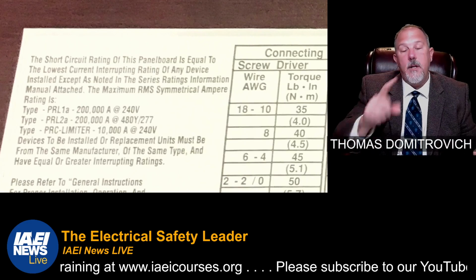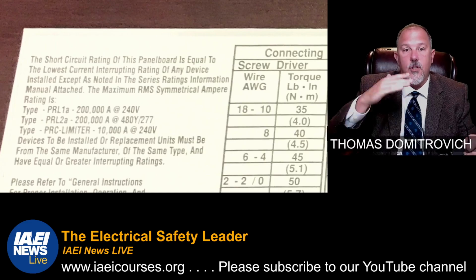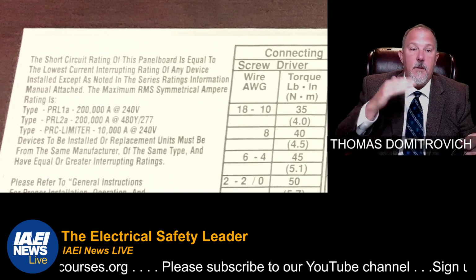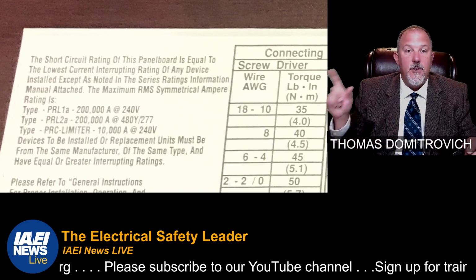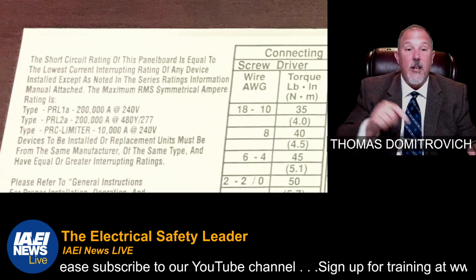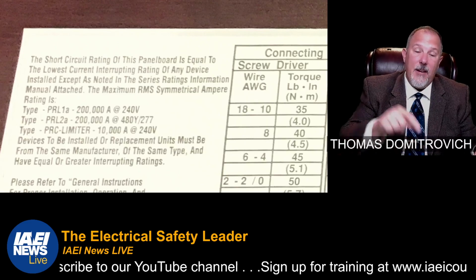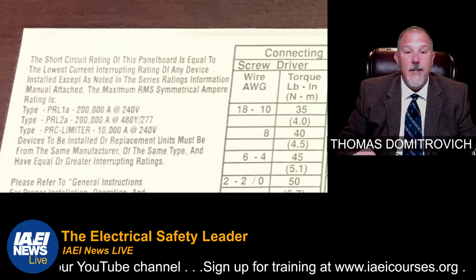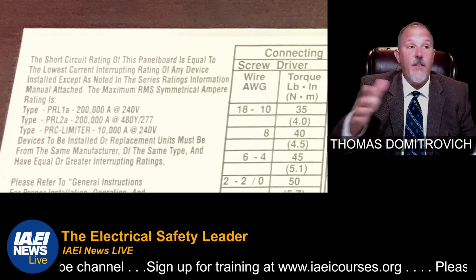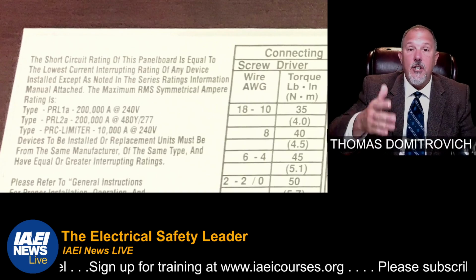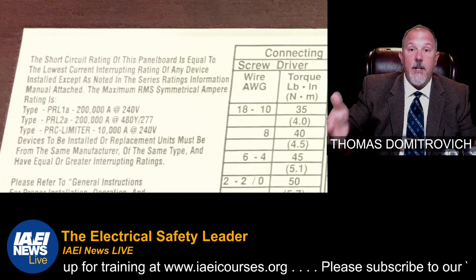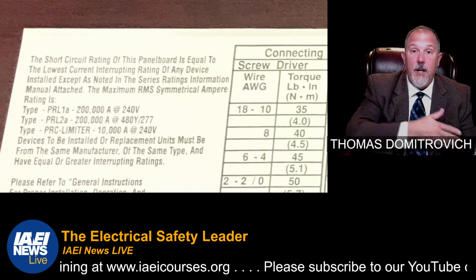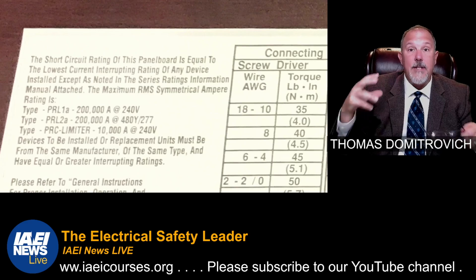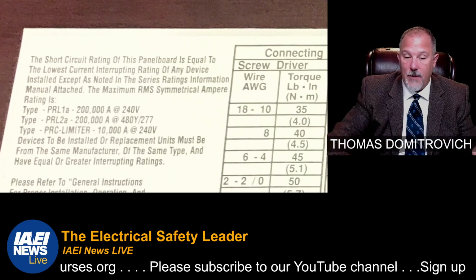And the moment you put it in that panel board, you've lowered the short circuit current rating of the panel board, because the short circuit current rating of the panel board is equal to the lowest current interrupting rating of any single device that's installed. And if it's a series rated system, you need to make sure that you get the exact catalog number that's a part of that series rated system. That's where the upstream and the downstream work together. And we're going to talk a little bit about that as well.